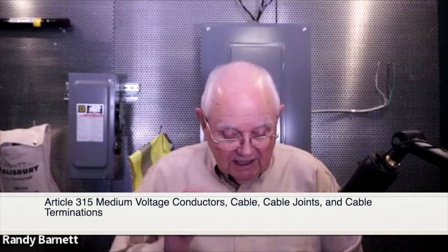Now today, I'm going to be using the 2023 National Electrical Code, and we're going to take a look at some of the requirements here. There have been some big changes for medium voltage systems, equipment and medium voltage cable in the NEC this year. We're also going to take a look at the construction and operation of the different components of this medium voltage cable. We'll take a look at the qualifications that the code requires if we're going to install this equipment. We'll also take a quick look at one of the articles in Chapter 4 on what they call high voltage equipment. So Article 315 is on medium voltage conductors, cable joints, and cable terminations.